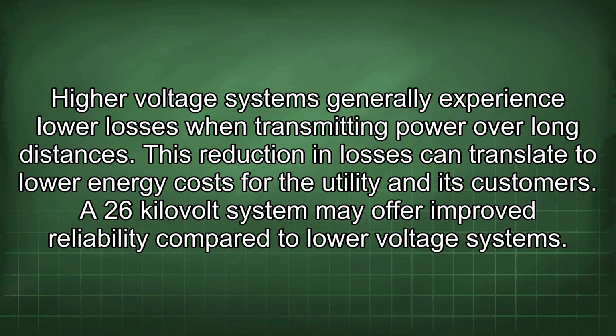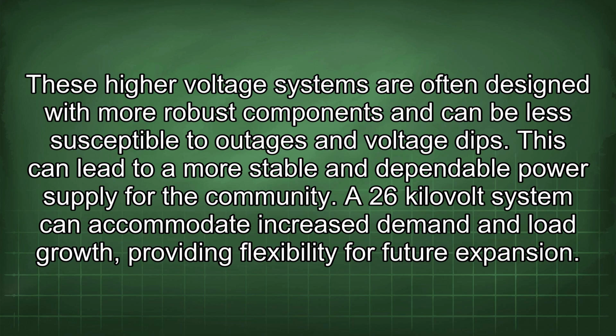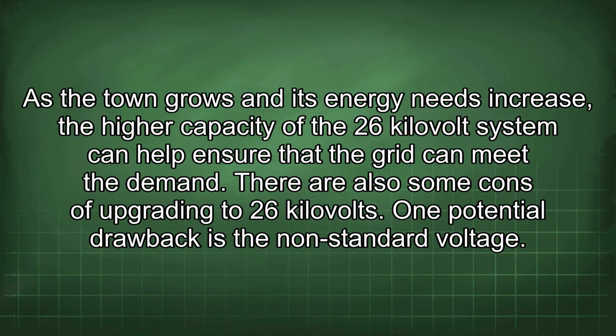A 26 kilovolt system may offer improved reliability compared to lower voltage systems. These higher voltage systems are often designed with more robust components and can be less susceptible to outages and voltage dips. This can lead to a more stable and dependable power supply for the community. A 26 kilovolt system can accommodate increased demand and load growth, providing flexibility for future expansion. As the town grows and its energy needs increase, the higher capacity of the 26 kilovolt system can help ensure that the grid can meet the demand.